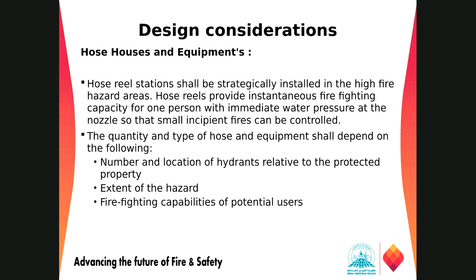The quantity and type of hose and equipment shall depend on the following requirements. The quantity of hose equipment is based on the number and location of hydrants relative to the protected properties, the extent of the hazards, and the firefighting capability of potential users. Those who are handling the fire hose cabinets, what is their potential to use that equipment in case of fire? Normally, the best practice is to install one fire hose cabinet for two or three hydrants. Each fire hose cabinet shall be located to serve 2 to 3 fire hydrants, so better to be in the range of maximum 3 hydrants.